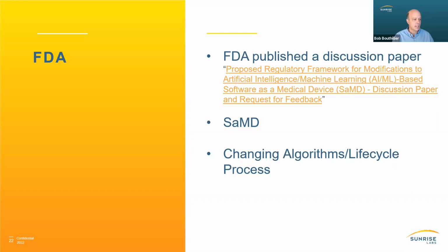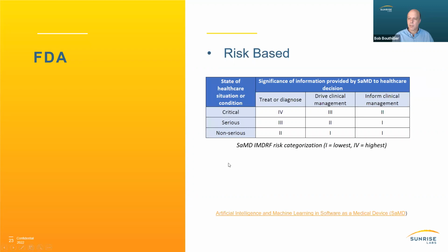If I scoot ahead to the next slide, there we go. They've actually provided an international group framework for software as a medical device, where, as usual, 1 is the lowest risk and 4 is the highest. They want every submission to consider whether the device in a future iteration could become a higher level of concern to the patient and thus to the FDA, so that you would have to treat the documentation accordingly. The link here is to the FDA website that describes all the current thinking on this, and it aligns very well with what they have done throughout history. It's a risk-based approach. If you have more risk, they want to see that you're taking more care.